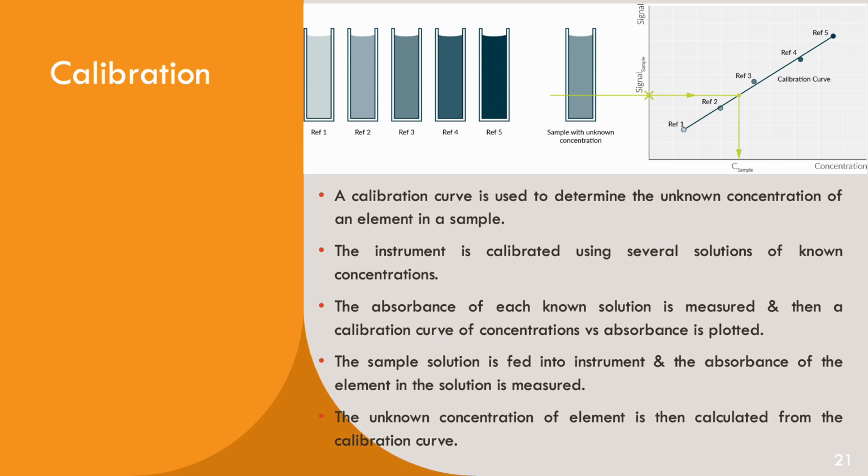The absorbance of each known solution is measured, and then the calibration curve of concentration versus absorbance is plotted. Then the sample solution is fed into the instrument, and the absorbance of that element in the solution is measured.